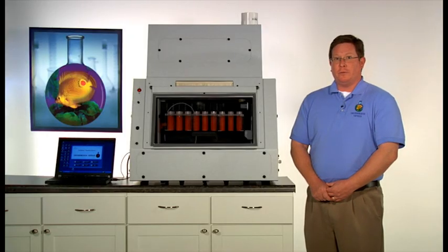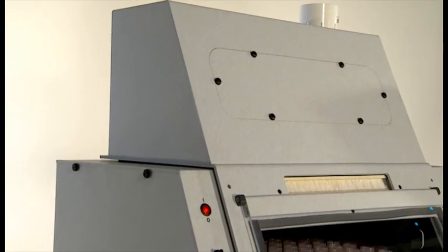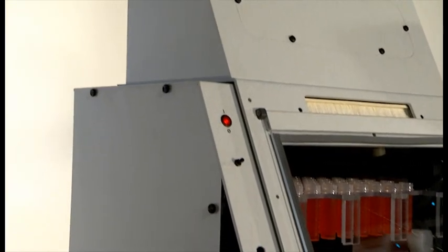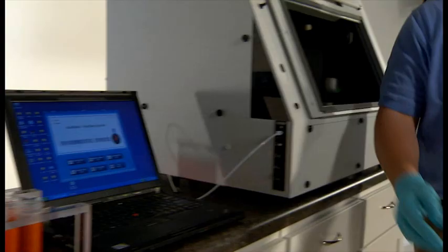The heating block uses heater mat technology. The AutoBlock also comes with an optional fume hood accessory, which frees up valuable laboratory fume hood space. To use the AutoBlock, prepare your samples in the Environmental Express digestion vessels and load them into the unit.